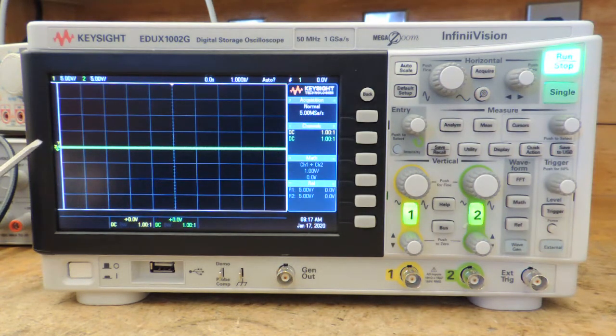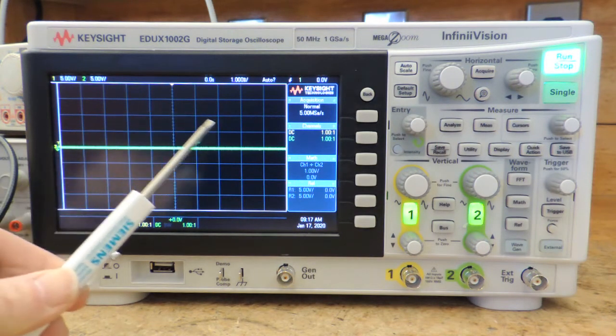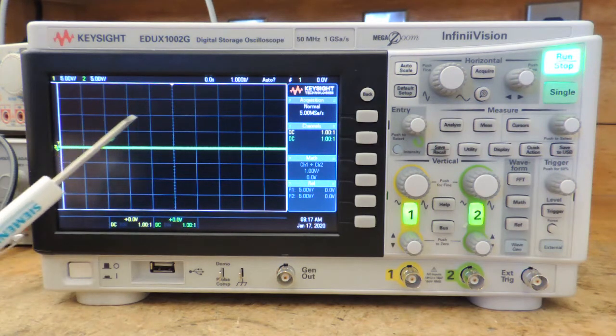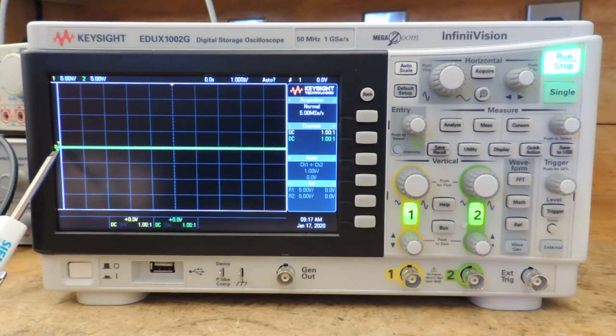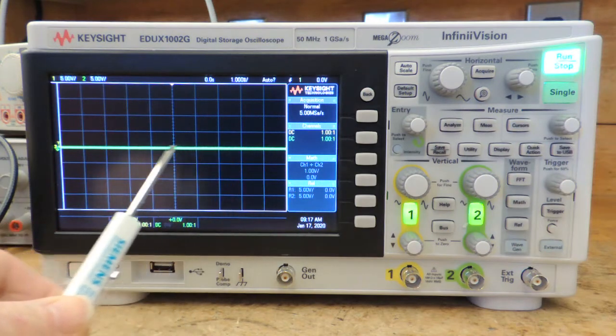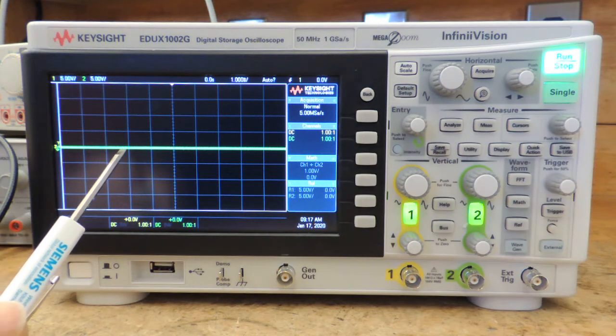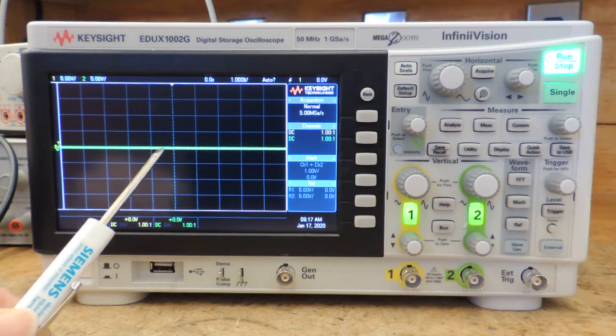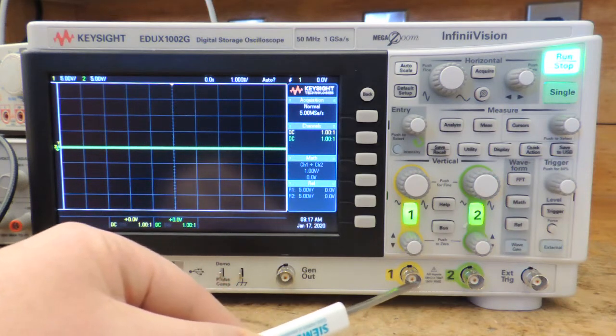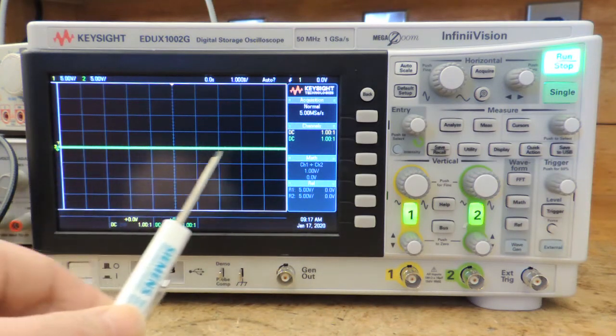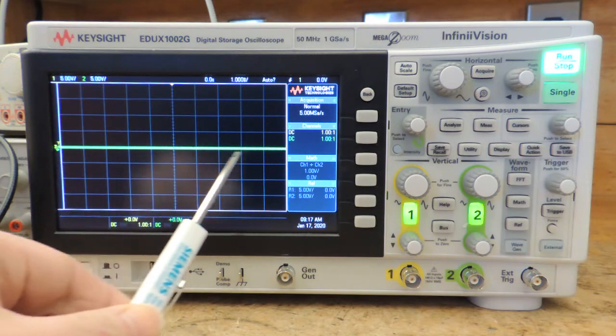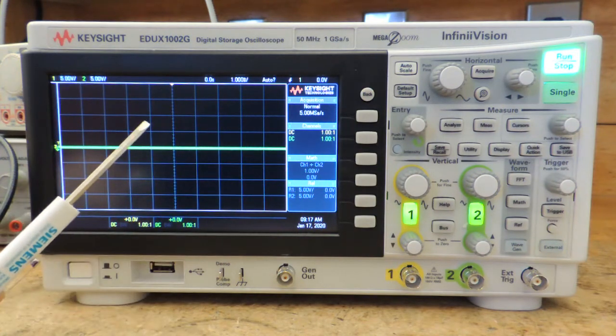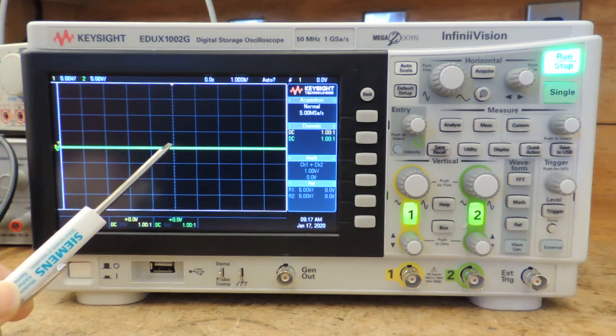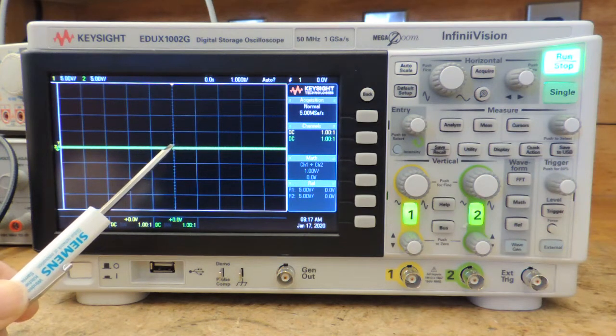So once it's started up, you can see that there are grids on the screen. The bright green trace that you can see on here is the trace that's coming from the input, and right now we do not have anything connected to our inputs, so we expect it to be a flat line along the zero axis. The grids are subdivided into 1, 2, 3, 4, 5 subdivisions within each grid position.